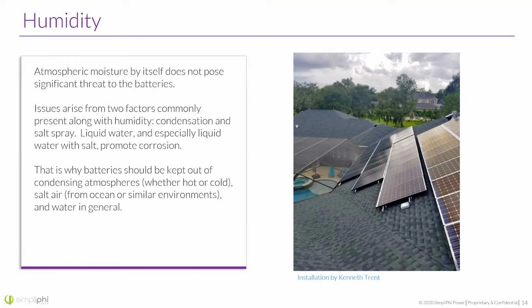So atmospheric moisture by itself does not pose significant threat to the batteries. Issues actually arise from two factors commonly present along with the humidity itself. That's condensation and salt spray. So liquid water itself is not good. If your room is so humid where the batteries are installed that it is dripping, there's actually liquid water present, that might cause an issue. That could cause damage within the battery. Maybe it leaks onto the battery and goes right into the battery. Maybe some condensation builds up around the edges of the battery. So that's where it becomes an issue. So we just kind of got to keep that in mind.